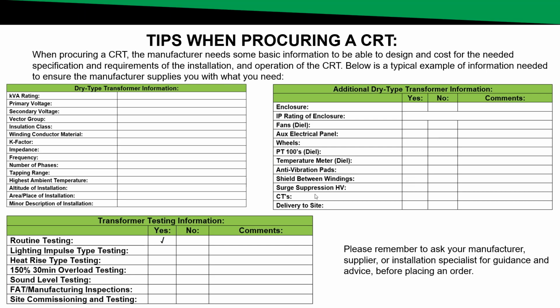Surge suppression device, CTs, and of course, do you want your manufacturer to deliver to site? Something to always keep in mind when you order your cast resin transformer is to tell your manufacturer you would like him to deliver, install or commission the transformer with you. This is always advised, as there are not a lot of experienced technicians around to actually commission and install cast resin transformers as needed.